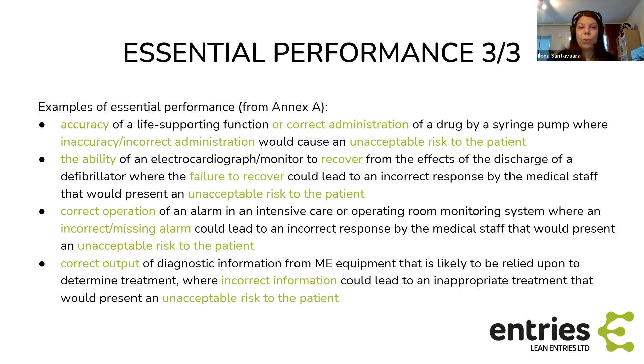Also, the term single fault condition is presented by the standard, and they say that the requirement must be fulfilled in a normal condition or single fault condition. So some requirements say this. And this ME equipment has to be designed and manufactured so that it remains single fault safe, or risk remains acceptable in those cases. And here are more definitions about when ME equipment is considered single fault safe, but I'm not going to go through those in detail, just for future reference.